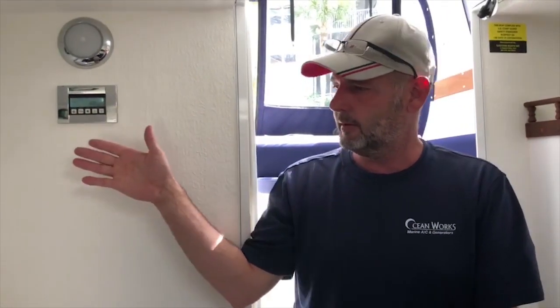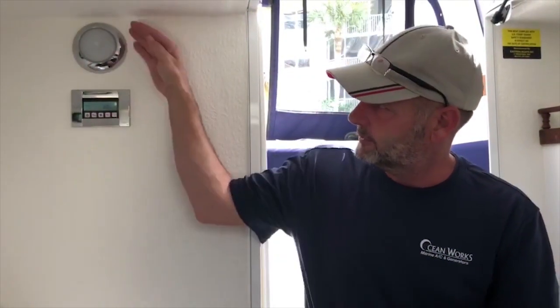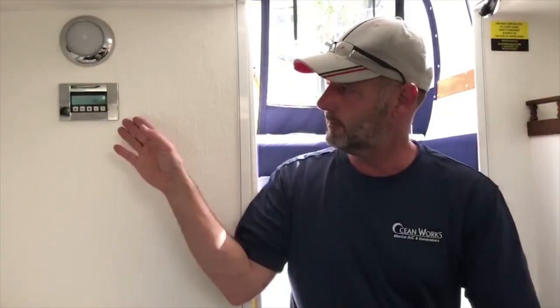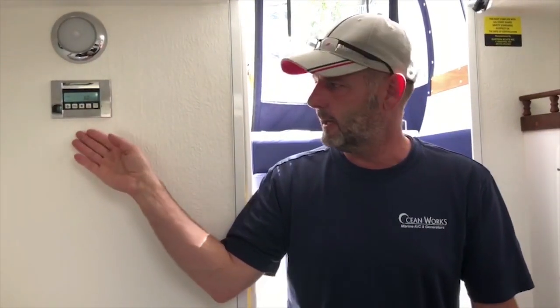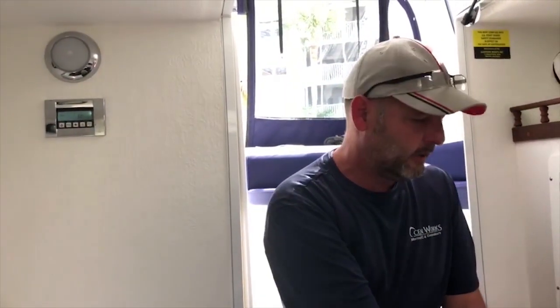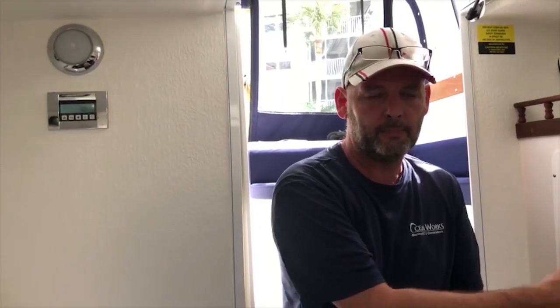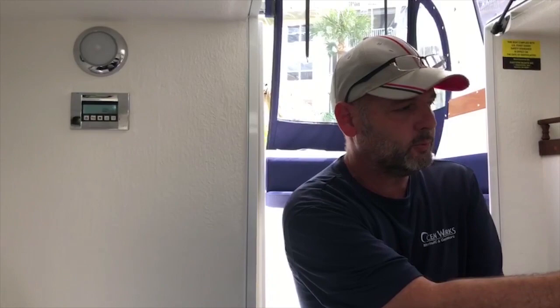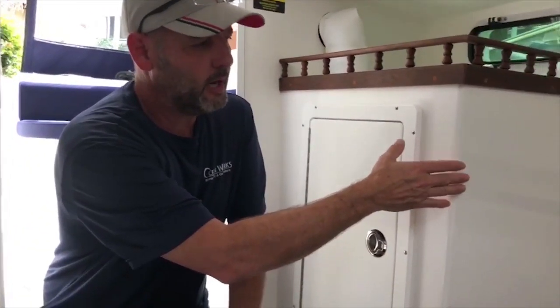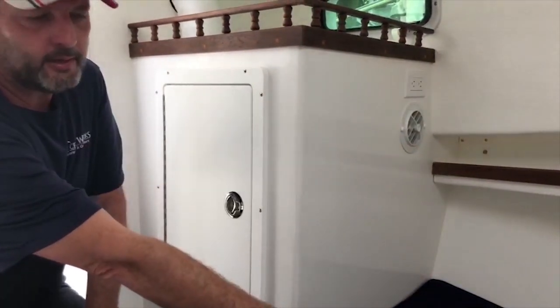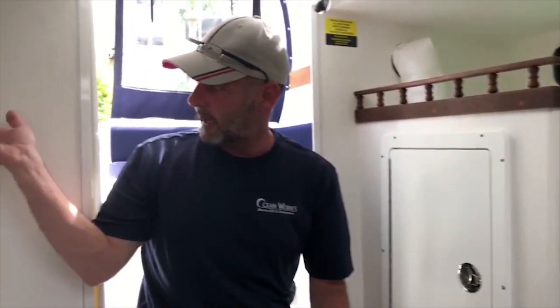In this case, we located the thermostat on the opposite wall, based on customer preference. He wanted it close to the other chrome matching fitting and wanted to be able to sit in this location to make adjustments. In general, you're looking for an interior spot where a customer can comfortably reach the thermostat, because the thermostat itself doesn't contain the sensor. The sensor that measures the boat's temperature is located at the actual equipment, a small bulb copper sensor placed in front of the evaporator. This gives versatility to put the thermostat in different locations, whether close to or away from the air conditioning equipment. One option would have been the front edge of the storage locker, where the customer could sit on the bench to adjust it, but he preferred putting it on this side instead.